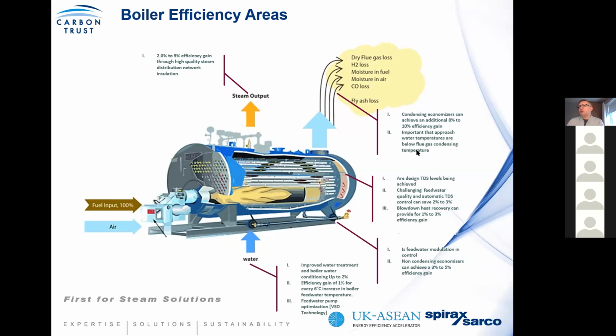So again, we should look at water treatment. Look at condensate recovery rates, because condensate is pure water or distilled water. So it's important to get condensate returned, but it's also important that you get it back at the highest temperature possible. For example, every 6-degree rise in condensate temperature is a 1% efficiency gain for your boiler.